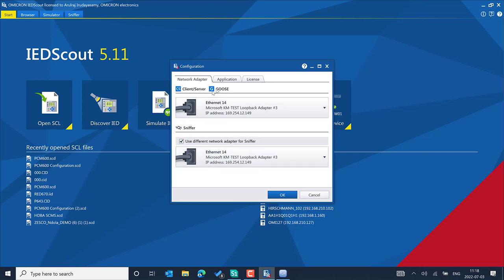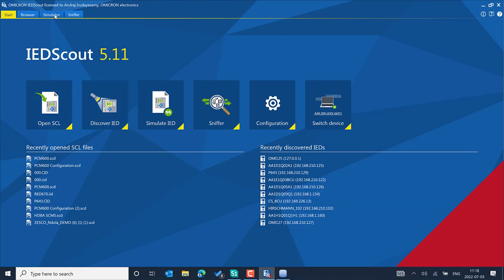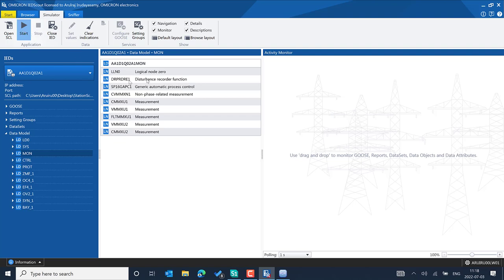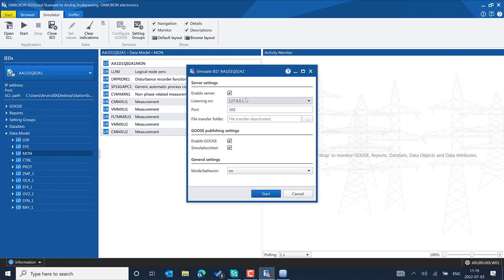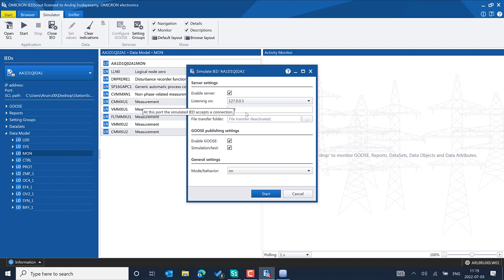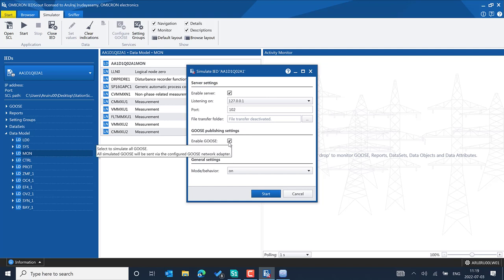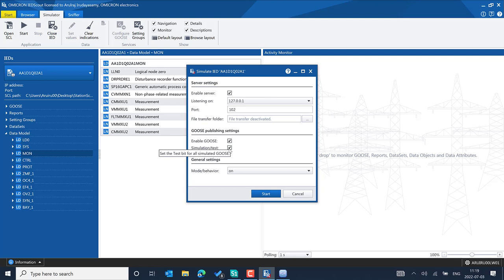You can also use the same adapter for the sniffer if needed. Going back to the Simulator, start the simulation. You can use the localhost IP address 127.0.0.1 and the default port. Enable the MMS server simulation on port 102 (the IEC 61850 MMS protocol default). GOOSE publishing is also enabled. By default, the simulation and test mode flag is enabled to avoid simulating GOOSE messages in a real environment — this keeps things safe.